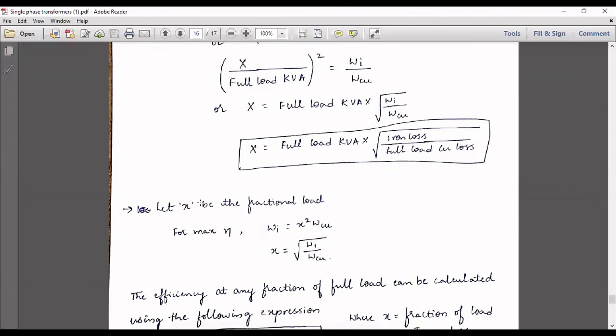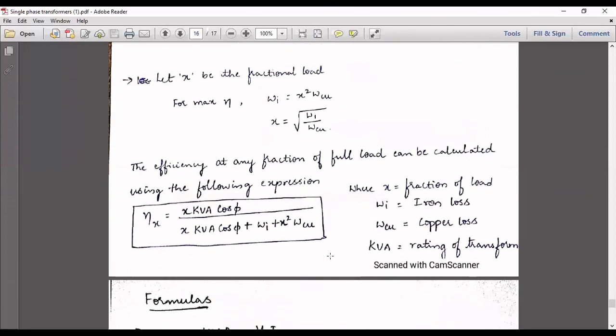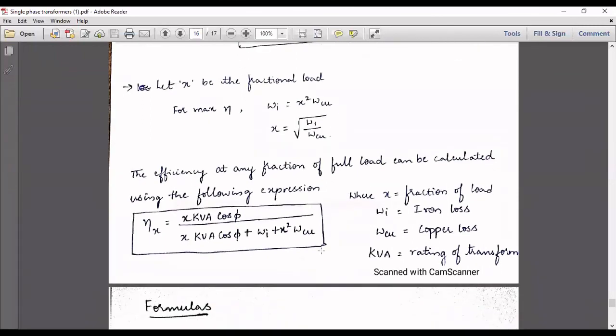If I take small x as the fractional load condition, then for maximum efficiency, Wi will be equal to x square WCU. So at maximum efficiency, iron loss is equal to copper loss, and x square is multiplied with the copper loss because it is a variable loss. This x is nothing but the fractional load value, which is always given by the square root of Wi by WCU. Whether the transformer is 100% loaded, or 50%, 75%, or 25% loaded, that load condition will be given by the square root of Wi by WCU. The efficiency can be obtained at any fraction of full load using the following expression.